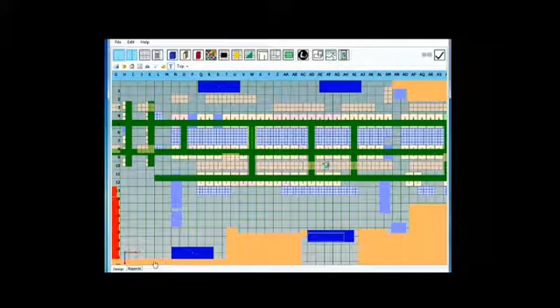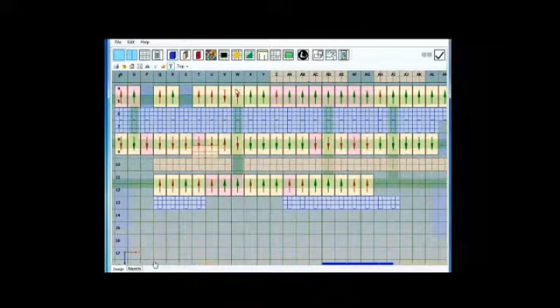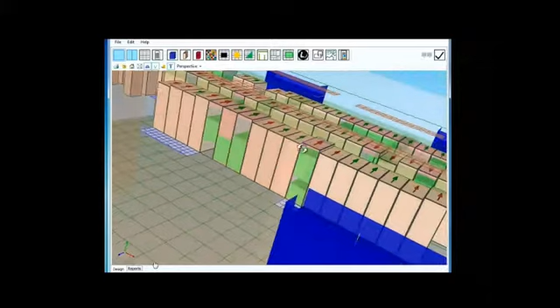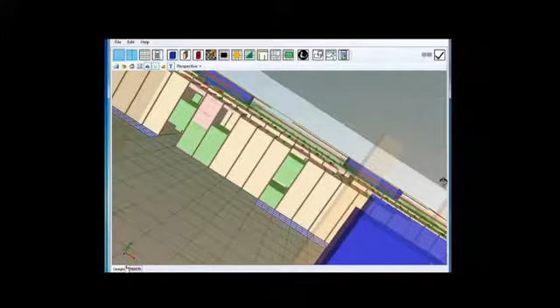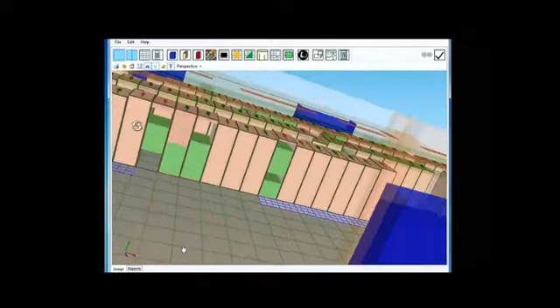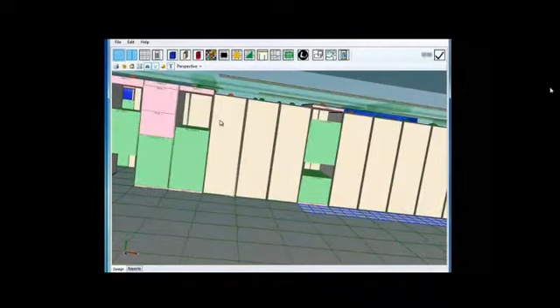I think the first thing of note, as with many data centers, is it didn't start as a data center - it was office space at one point, so it's not a perfect box. Primarily, the majority of the rack infrastructure is located down that center aisle of the space, and you can see the 5 perimeter CRAC units scattered around the room. It was something that evolved over time, so they weren't optimized from a layout perspective - they were just added as capacity was required.